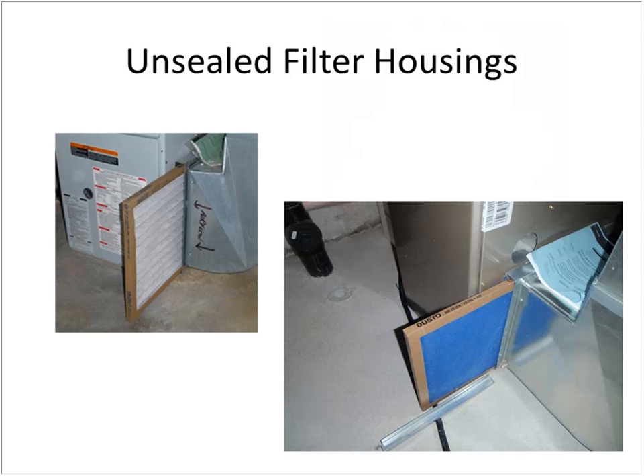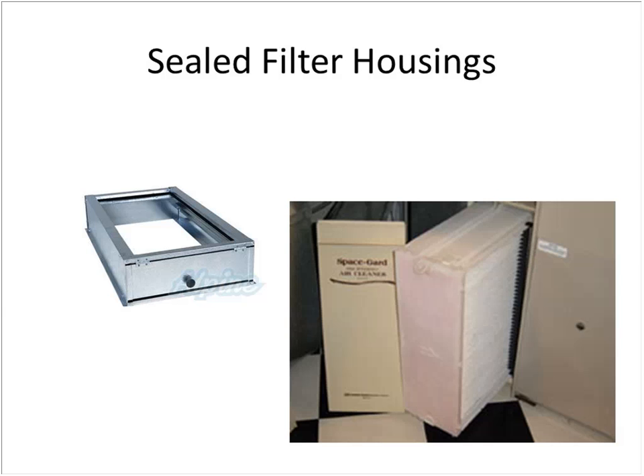Some of the areas that we typically find that fail in our inspections from a leakage standpoint is that they do not have the mandated covers on the filters, and there are a couple of different housings. The one on the bottom right has a metal crimped seal, but that's not really sealed that well. In my opinion, the only effective seals are the pre-manufactured housings for filters that have a gasketed seal on them. These are some of the examples. Now these are high efficiency media filters, but they also have filter housings for the standard 1-inch filters that you might consider installing.